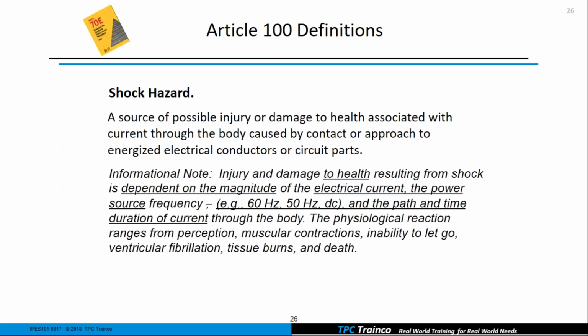They gave us a new informational note for shock hazard. The informational note is now talking about injury and damage to health, and it tells us that shock is dependent on the magnitude of the current, the power source, and the frequency, which has a huge determination in whether we're going to get hurt or not, and the path and the time duration. So they did a lot with shock and statistics with their new Annex K.